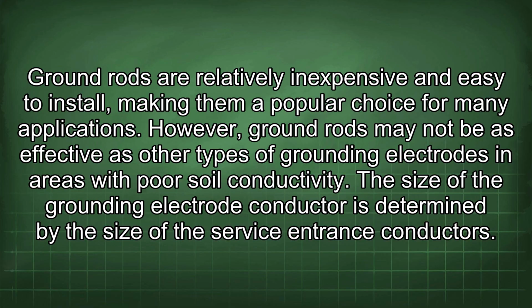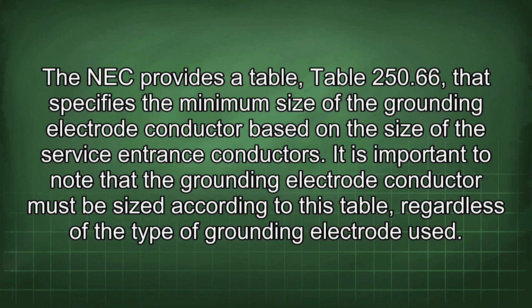The size of the grounding electrode conductor is determined by the size of the service entrance conductors. The NEC provides a table, 250.66, that specifies the minimum size of the grounding electrode conductor based on the size of the service entrance conductors. It is important to note that the grounding electrode conductor must be sized according to this table, regardless of the type of grounding electrode used.